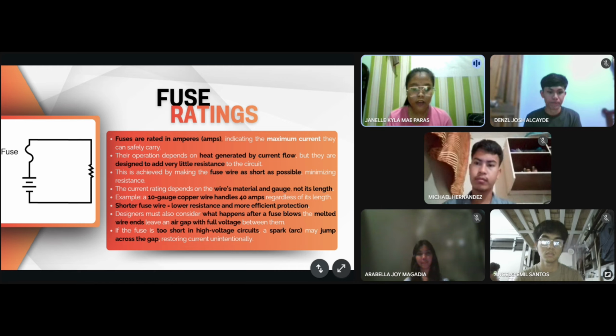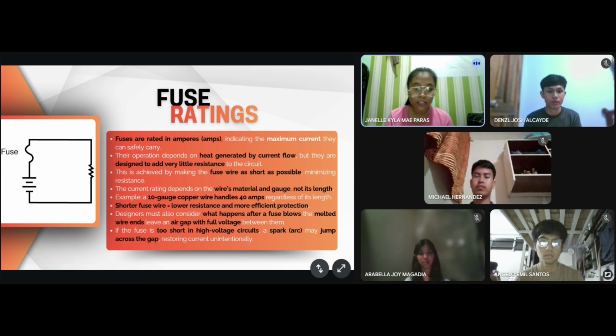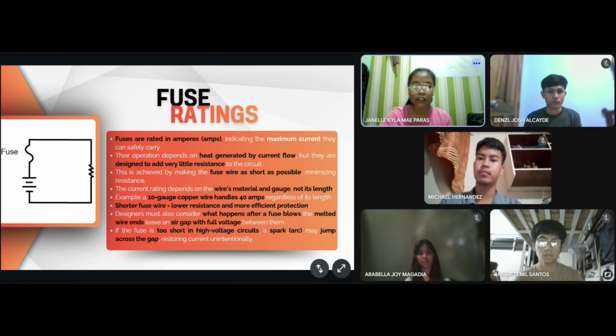A shorter fuse wire has lower resistance and provides more efficient protection. However, when a fuse blows, the melted wire ends may leave an air gap with full voltage between them. If the fuse is too short, especially in high voltage circuits, a spark or arc may jump across the gap, causing the current to flow again unintentionally. Therefore, careful design and proper fuse rating selection are essential to ensure safety and reliable circuit protection.